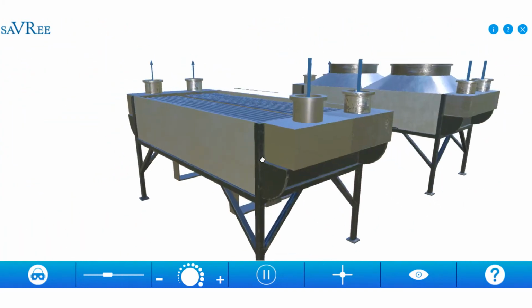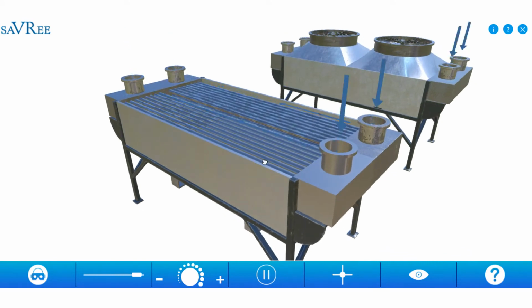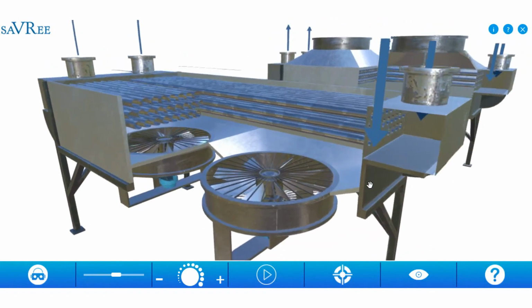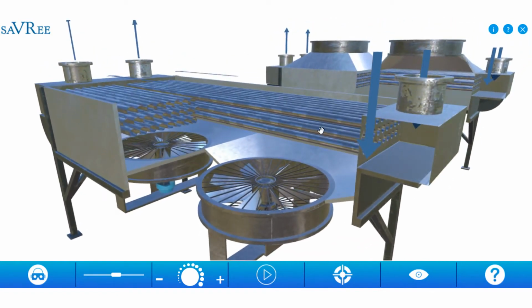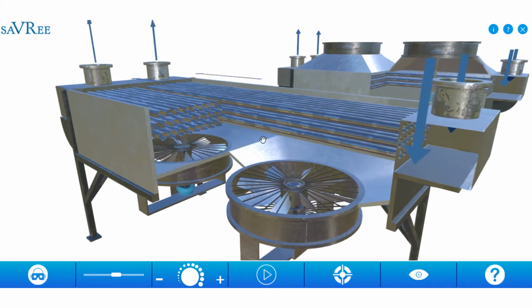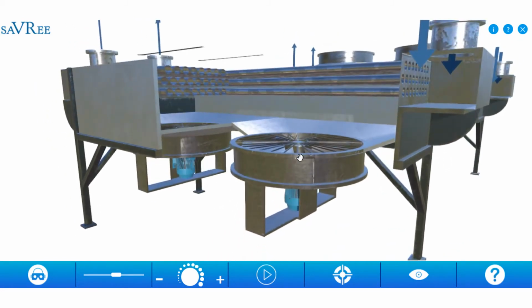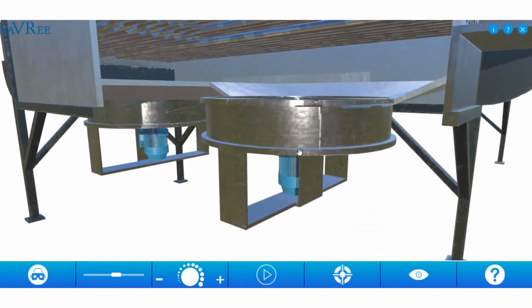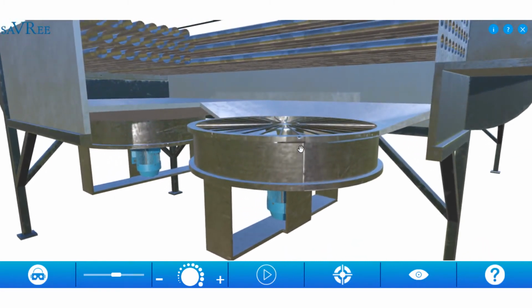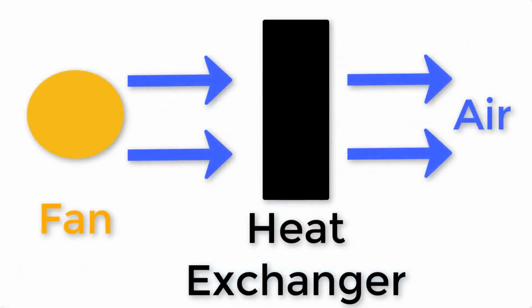So this is a heat exchanger, similar to a shell and tube type heat exchanger. If I just pause that for a moment, I'll take the cross section again. So the fluid is coming in the pipe here, it passes through these tubes and then goes out. That's a standard sort of heat exchanger arrangement, and we've got a forced draft setup. What that means is the fan is placed before the heat exchanger, and then we'll force air across the heat exchanger. That's a forced draft setup, or mechanical forced draft setup.